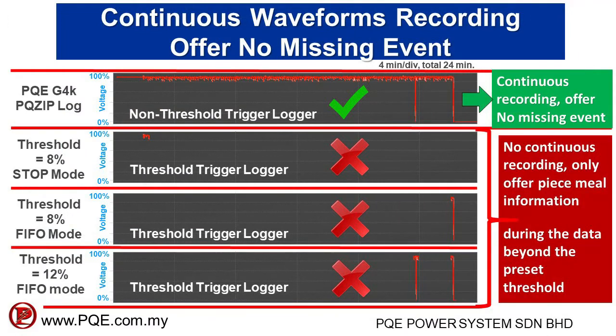For voltage dip measurement, we emphasize the importance of having continuous voltage and current waveform recording based on a non-threshold trigger method. A power quality analyzer with continuous waveform recording mode will be able to capture any event in your network. Analyzers that adopt a threshold trigger mode are not suitable for standard power quality voltage dip monitoring, as they will not continuously capture three-phase voltage waveforms and therefore cannot help you maintain a stable and reliable power system.